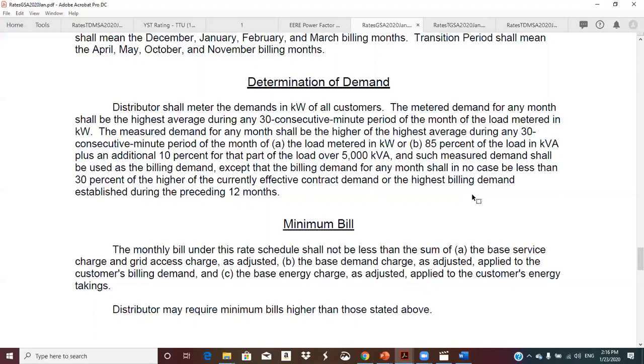So if your power factor is above 85%, taking 85% of the kVA will give less than the kW. But if your power factor is lower, say 0.6, taking 85% of kVA gives a much bigger number than kW. And they say, fine, I'll just charge you for the bigger one. That's what that calculation is doing.